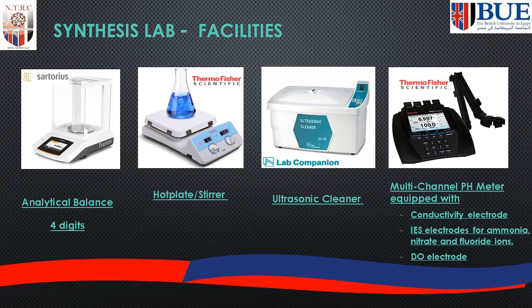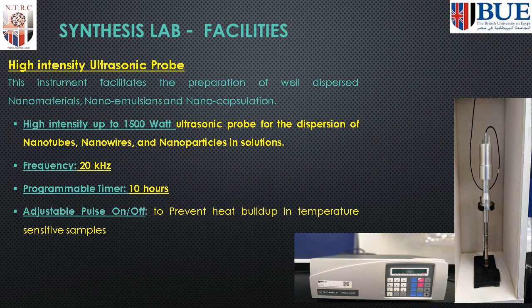This technique has been used for preparation of well-dispersed nanomaterials, nanoemulsions, and nanocapsulation using the sonochemical method. This device shows high intensity up to 1500 Watt with frequency of 20 kHz. It has a programmable timer reach up to 10 hours. Also it has an adjustable pulse on-off option to prevent heat buildup in temperature-sensitive samples.